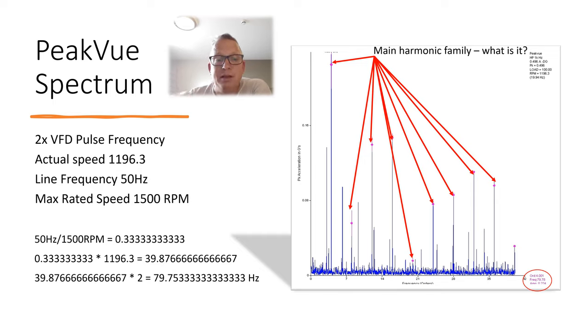Gives us 79.75 hertz, which is this frequency here. So we can know that this here is not a bearing defect, it's your two times pole frequency.